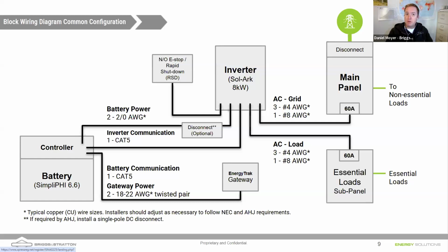Given that you have a 200 amp breaker and a 200 amp bus, with the 120% rule, it'd only be a 40 amp breaker. Now, with some of the PCS controls that are now UL listed, we can have 60 amps, right? So we want to be able to pull 60 amps from that panel to supply the loads, but we want to be careful not to backfeed more than 40. And we're going to talk about this in a minute on an upcoming slide, how we can limit that grid sell to not exceed that 40 amps of backfeed. So it's really cool features that are now coming onto the market with these PCS controls.